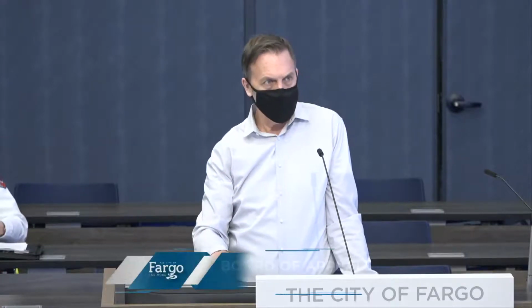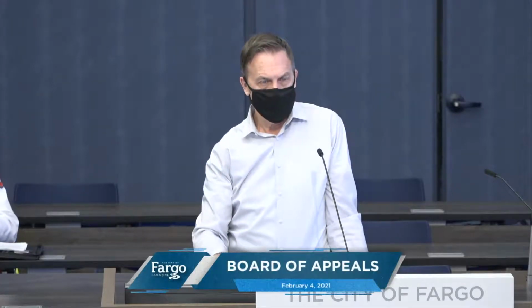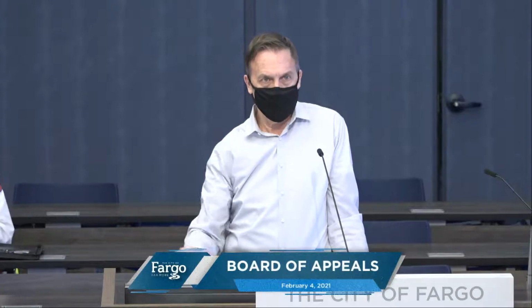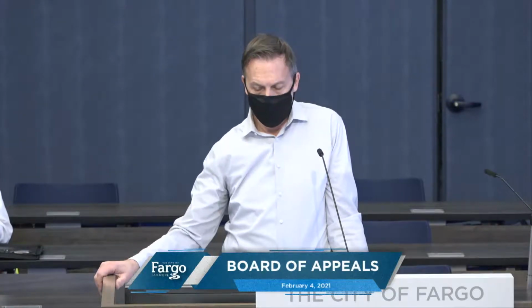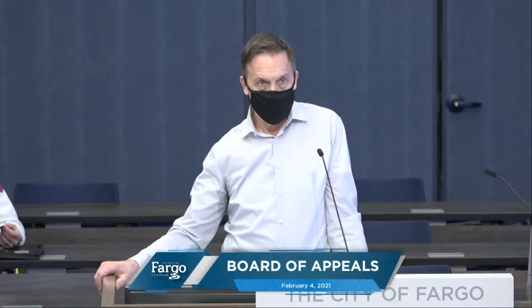You guys know with fire barrier, when we start talking about opening protectives, joints, seals, holes, pipes, anything that goes through. That building can have holes anywhere it wants, because it's 1 hour construction. It's not a 1 hour fire barrier. It'd be different if it was. So if we're able to prove that it is, it states it in the plans.